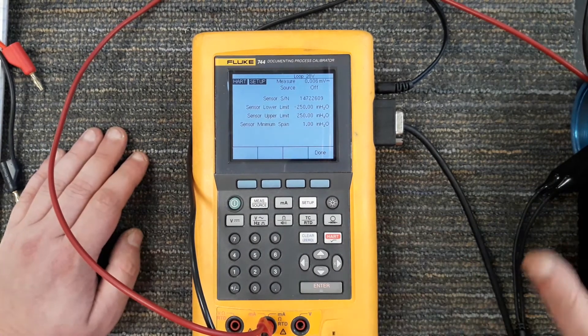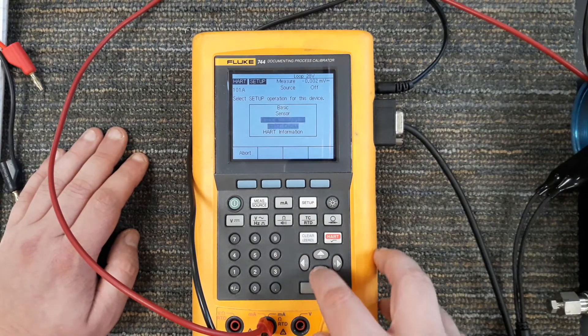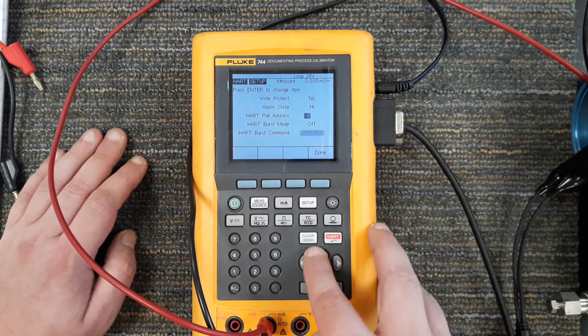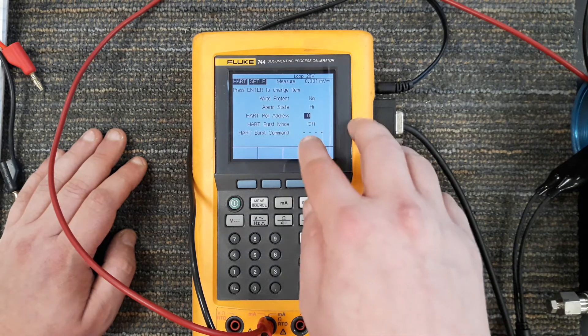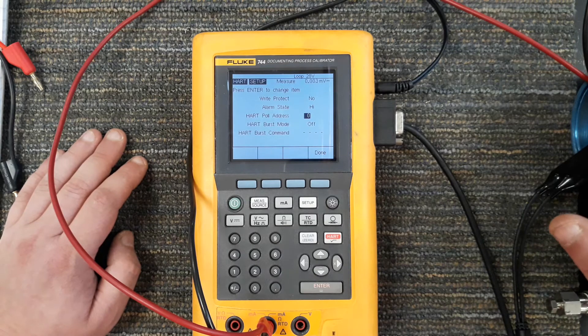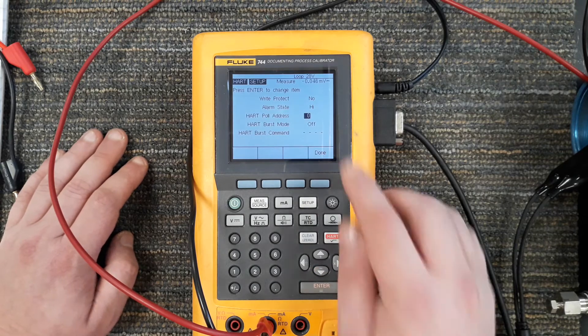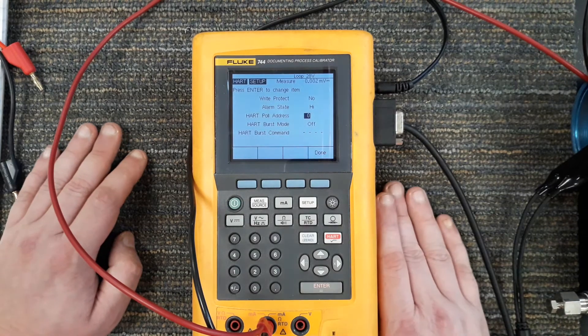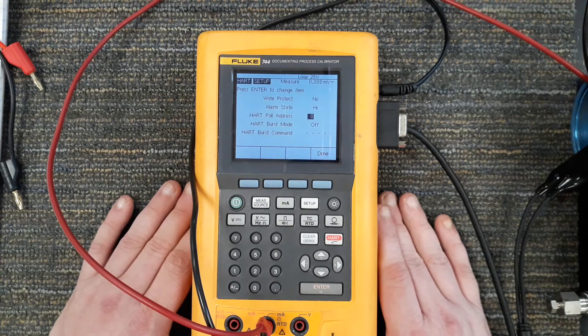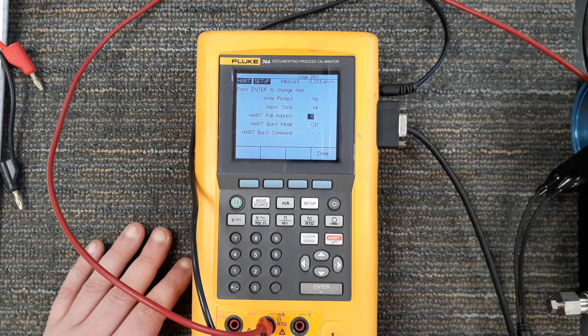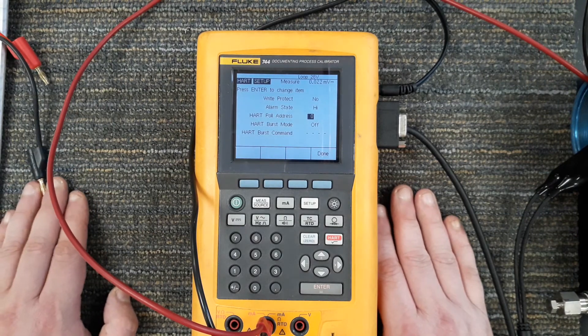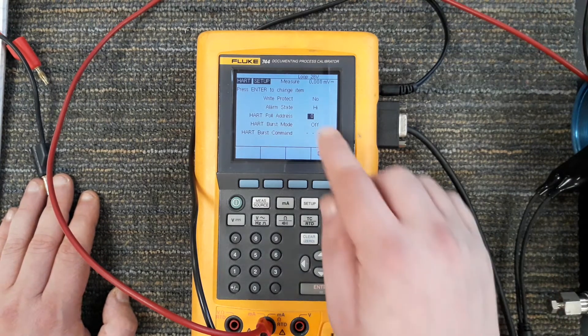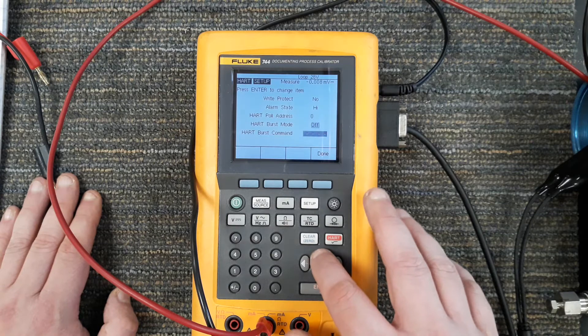Device identification, HART output. This is where I can set the alarm state, HART poll address, which you'll learn in other classes. If it's a HART device, just a standalone with its own loop power connects to the DCS on itself, the address is always going to be zero. If you give this device any address other than zero, then the device automatically thinks it's in a multi-drop situation and that will mess things up if you're trying to treat it as a standalone instrument loop because it's going to park its milliamps at four milliamps and never change the output. If you notice a transmitter that's just stuck at four milliamps all the time, you might want to check to make sure that its polling address has not been changed from zero.